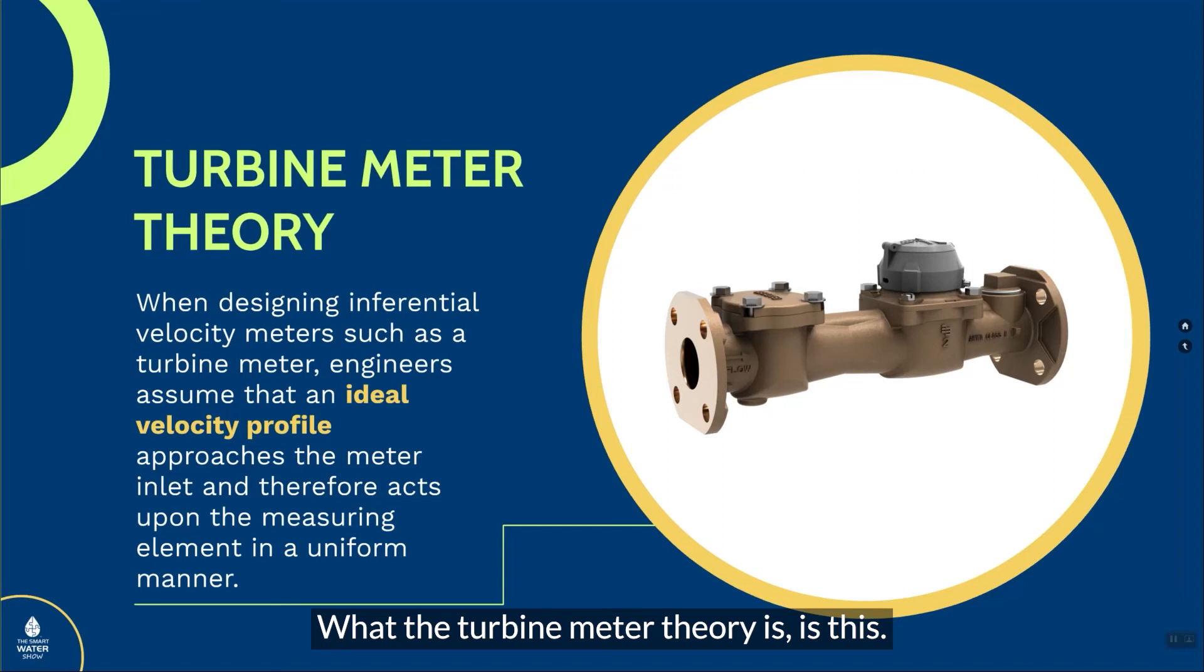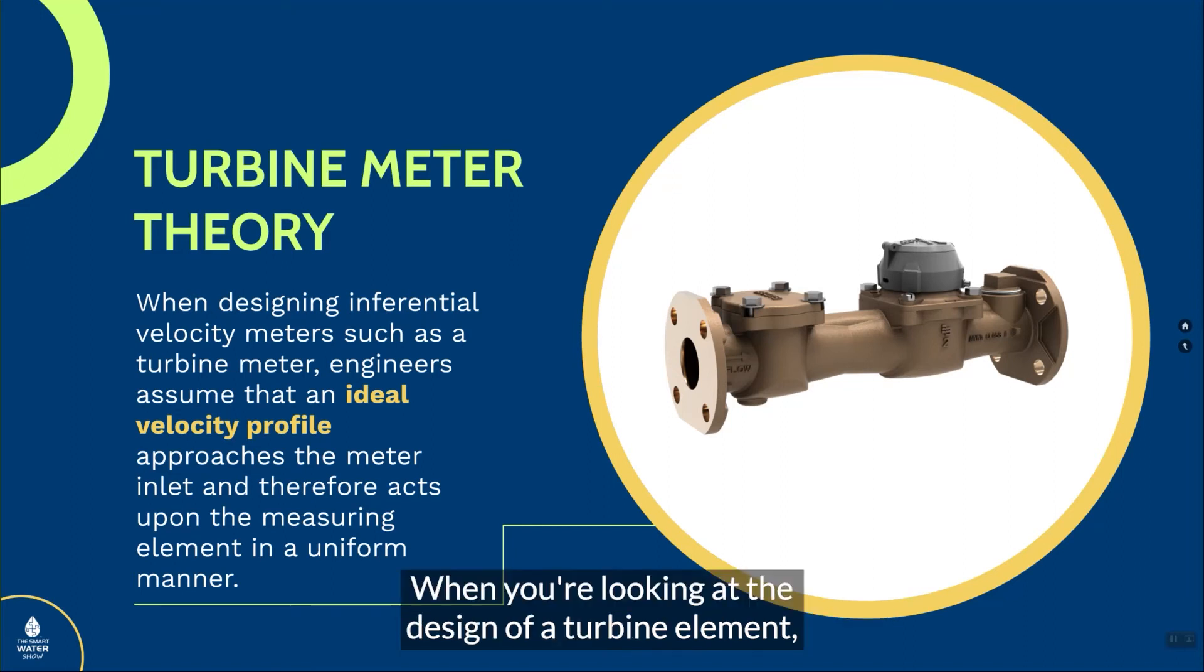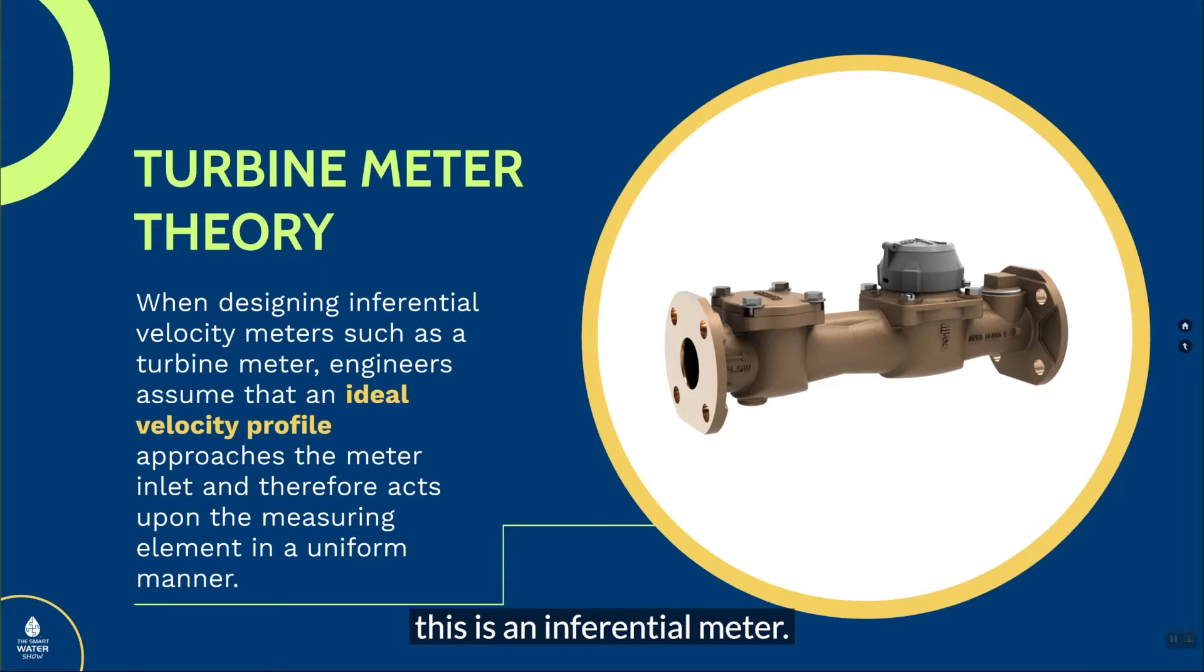What the turbine meter theory is, is this: When you're looking at the design of a turbine element, this is an inferential meter. It's inferring a velocity into a volume. In order for that to work correctly, the engineer that designs this is assuming that I have an ideal velocity profile.